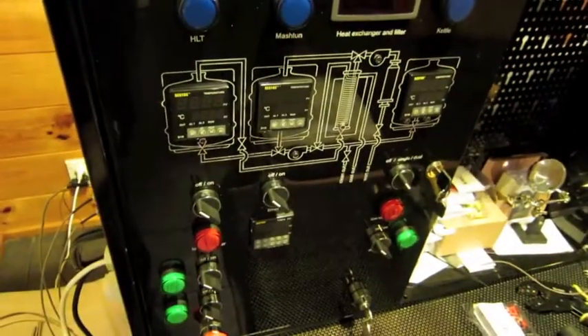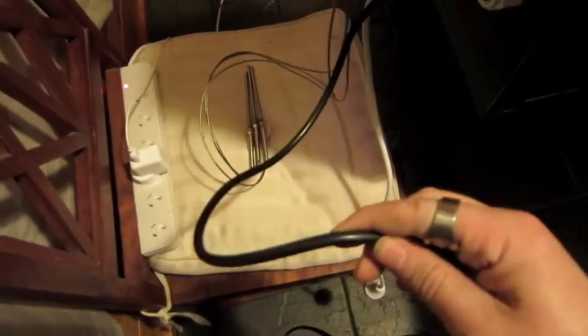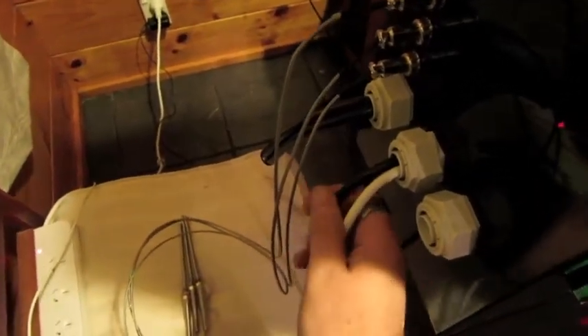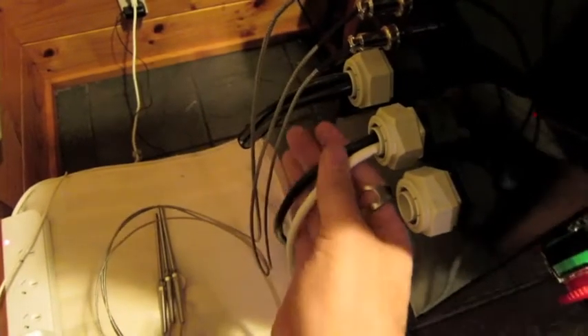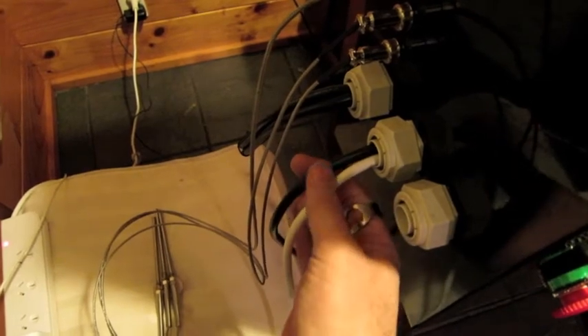And then another power line, power cable that comes in to control the power that goes to the elements. And that may have multiple cables coming in because I want to keep everything under 10 amp rating. So I'll have one cable that will look after one element and another cable to look after another one, so they're all on separate 10 amp circuits.